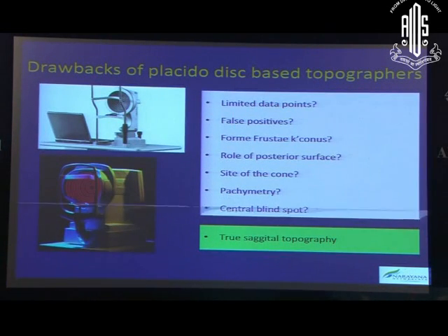So if I look at the drawbacks of all these Placido-based devices or topographers, they have limited data points. They usually can give you topography from the central, I would say, 6 to 7 millimeters maximum. Beyond that, it does not give you anything. There's a camera in the center, so the central topography is actually simulated.